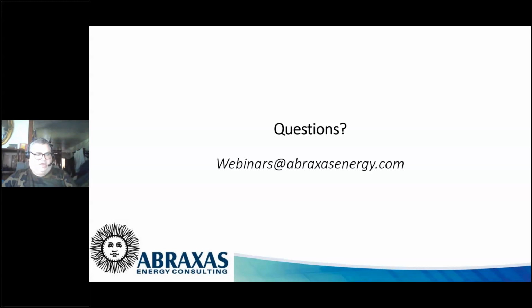Where it gets into the energy management side is people like me start operating between 100% and 40% and say, okay, I need to do better. I know where the top end is. Now I need to know where I can go from here to reduce energy. Commissioning helps in energy management, but it's not based on energy management. Retro-commissioning is, but the commissioning of a new system doesn't necessarily focus on energy. They're not focusing on operation. I want to make sure that this thing operates across the spectrum. I don't care to optimize for energy management. So retro-commissioning, people like us, that's where we step in and say, okay, we can do better. Right. But that's set at TAB. That's set at the original maxed out point. Okay, here's another one.